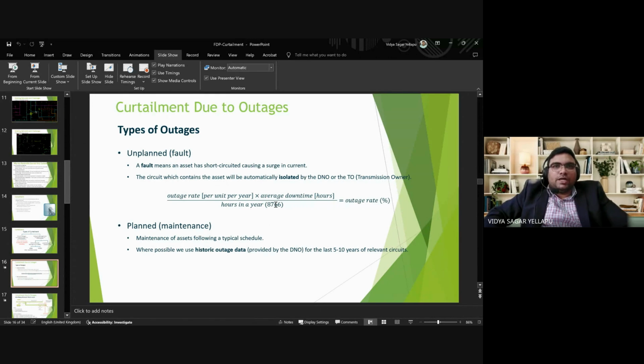Planned maintenance. If there are planned maintenance activities of the key assets pertaining to a particular distributed energy resource, since that is getting maintained, it cannot export power, and if it is a battery, it cannot import as well. So for that particular duration, the project is to be curtailed. These planned outages are due to maintenance of assets following a typical schedule. For modeling the impact of this planned maintenance, or the curtailment due to these planned outages, we can use historic outage data of various assets and how those are getting maintained over time. That gives us an estimate for the curtailment for a particular project.